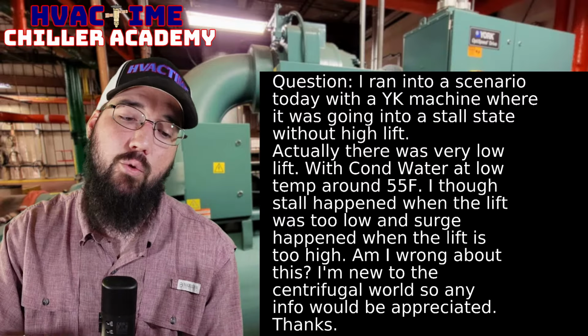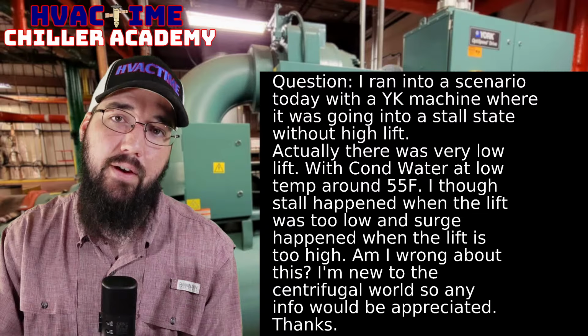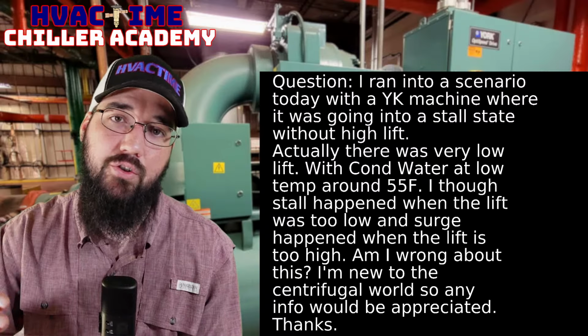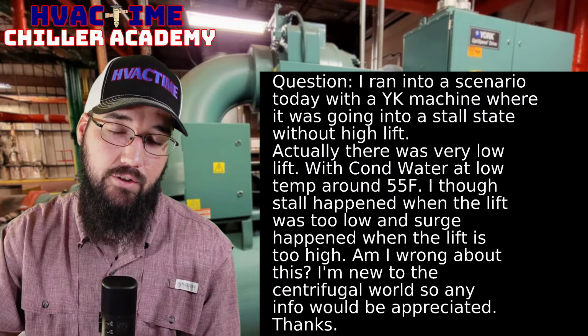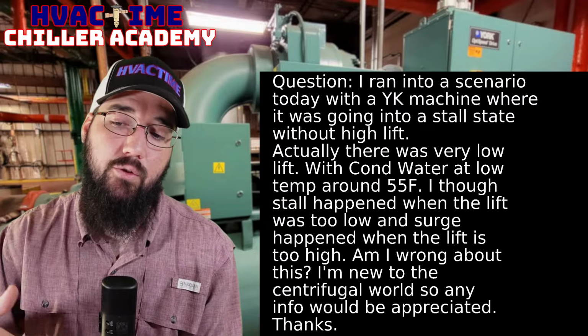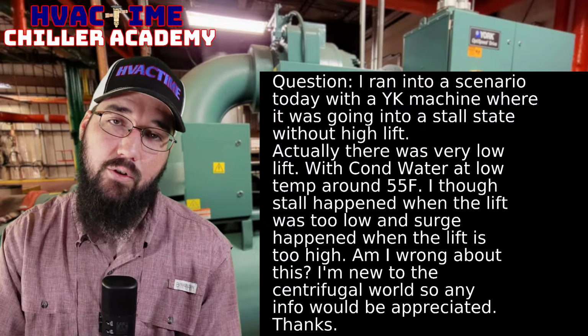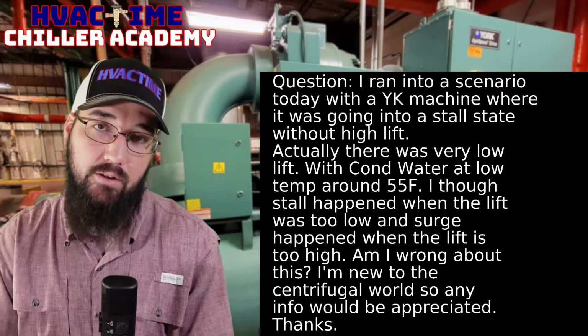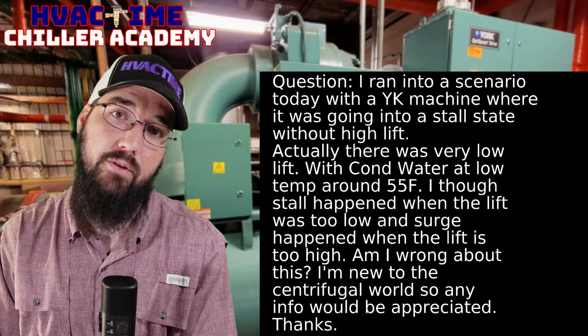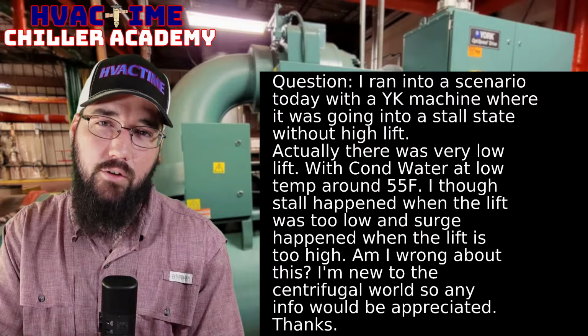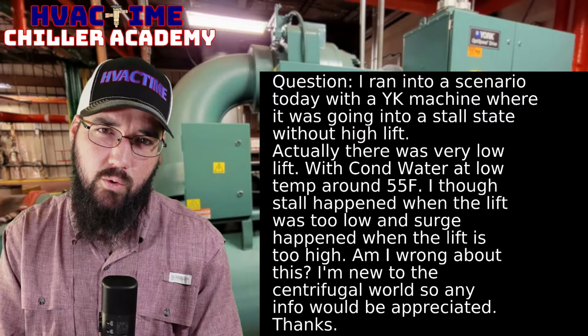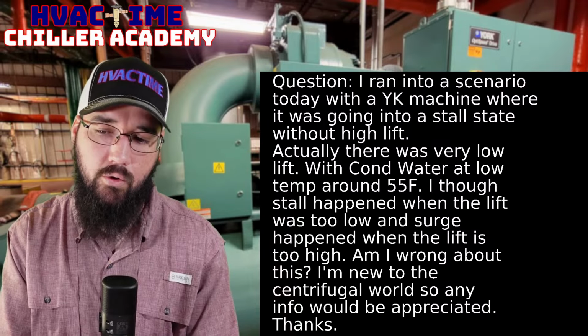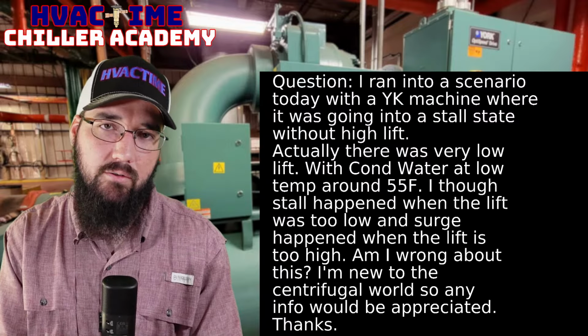Getting back to the speed, it has an effect on what our surge ceiling can be, or lift ceiling, I should say. So if we need to maintain a higher lift or a higher ratio, then we have to speed the compressor up before we can open the vanes more. Is that making sense, how these things are correlated and directly tied? I really hope so. This is a very advanced topic, right?